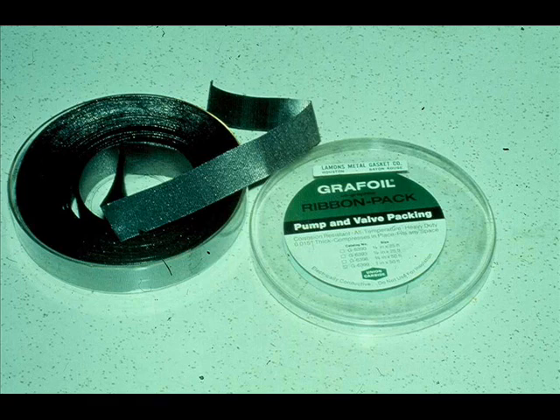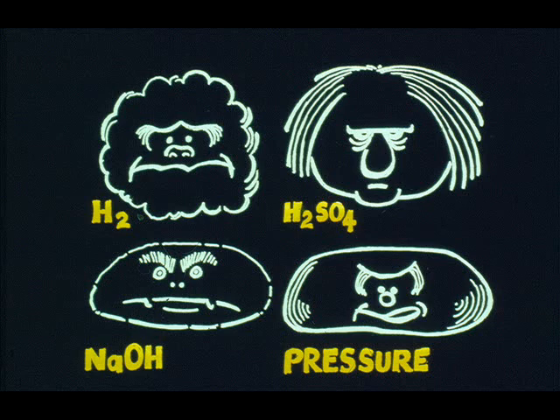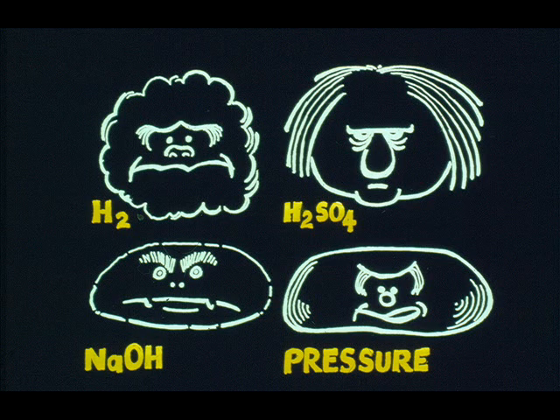Grafoil is another multipurpose packing. It is an all-graphite material that requires no lubrication. Grafoil can tolerate temperatures in excess of 1200 degrees Fahrenheit. Severe services such as hydrogen, acid, caustic, or extreme pressure require special packing and lubricants.